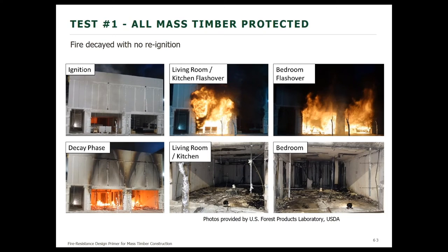So here we are. These are just a few slides that show basically the progression of the test itself. Over on the left side, you can see the glow in the lower left unit. That's right after they started the ignition. In the living room, the fire on this side was then in the flashover stage in that picture. Next picture, we have the adjacent room, the bedroom area, in flashover. Then it moved to the decay phase, and then a couple of pictures as it basically self-extinguished.